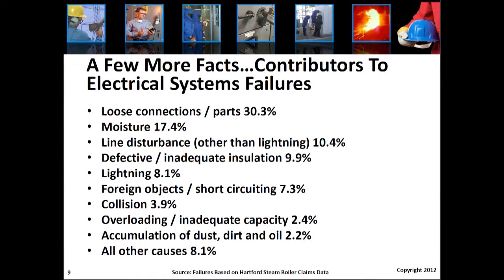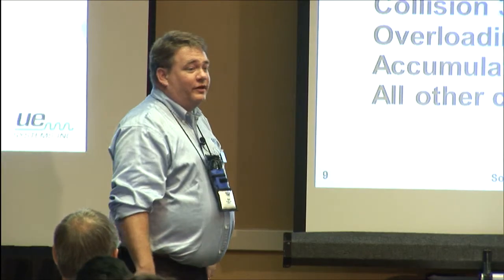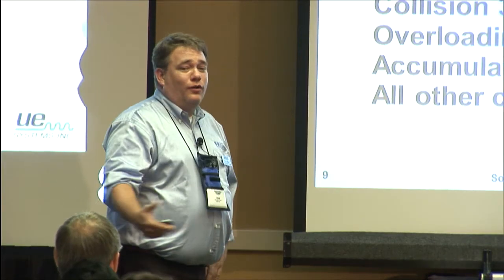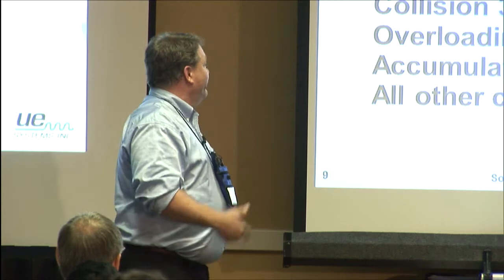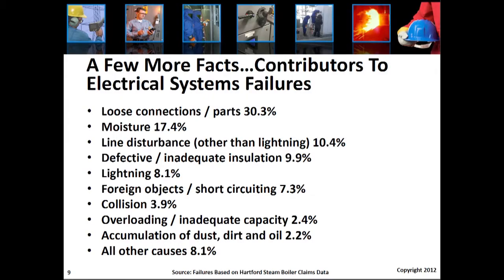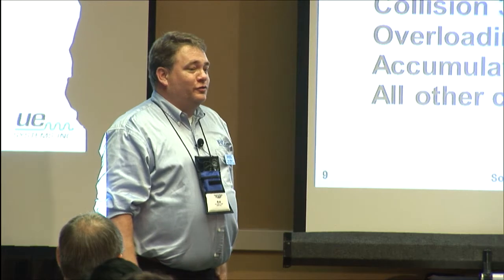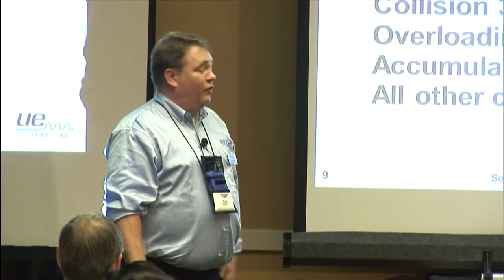Lightning—nothing much we can do about that, other than better grounding. Foreign objects and short circuiting, 7%—somebody dropped a wrench, a squirrel got in the cabinet during the night. Collisions—somebody on a forklift just not paying attention. And the generics: overloading, inadequate capacity. Are you running it at the level it's supposed to be, or is it consistently overloaded?